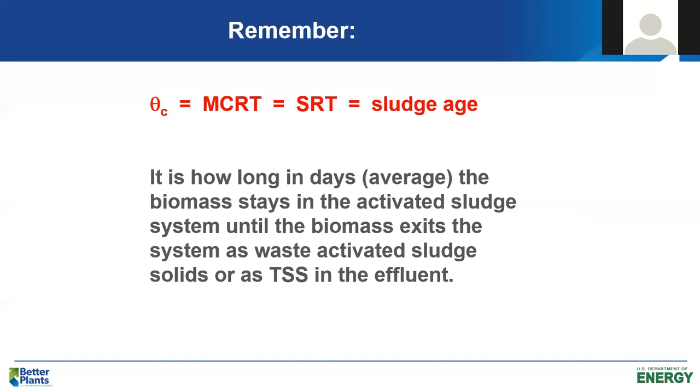But what I want you to understand is once you choose one of those operating parameters and you operate at a certain value for that parameter, you automatically set the other three values, whether or not you calculate them. So we need to keep that in mind. And again, we set those parameter values by controlling the activated sludge, the biomass in the process.